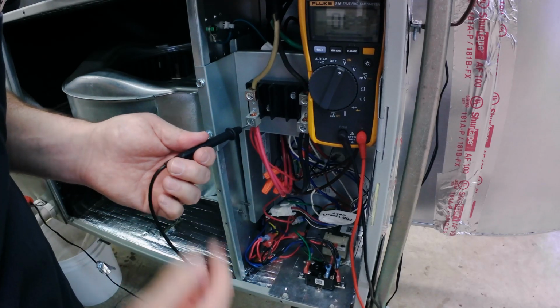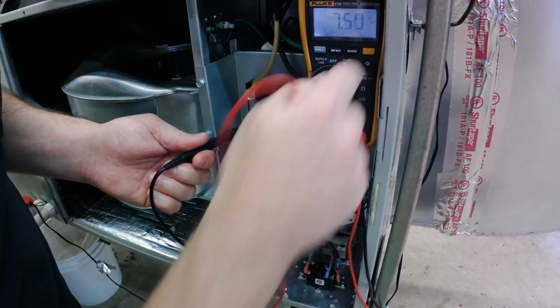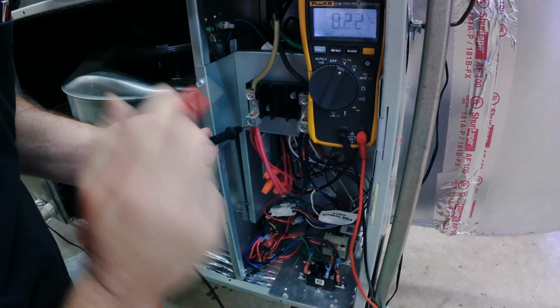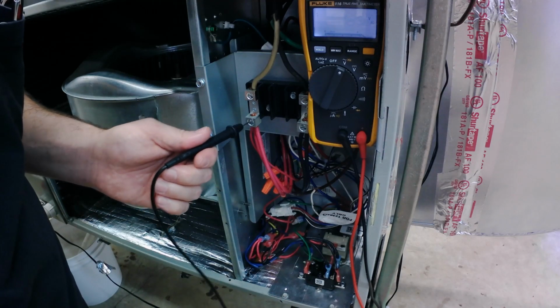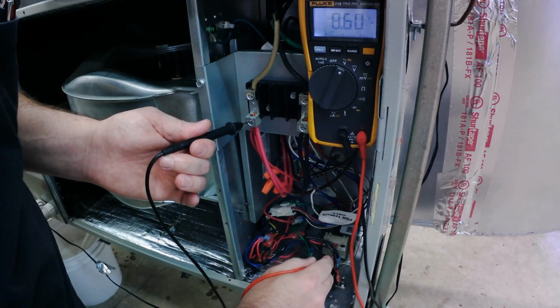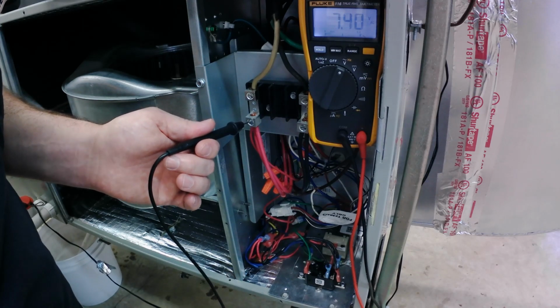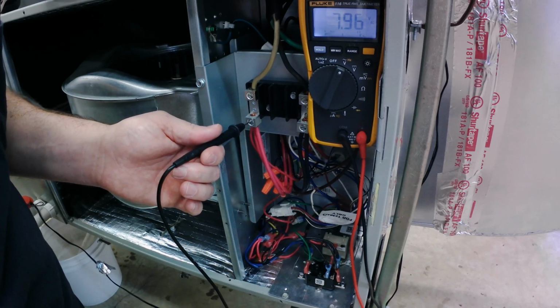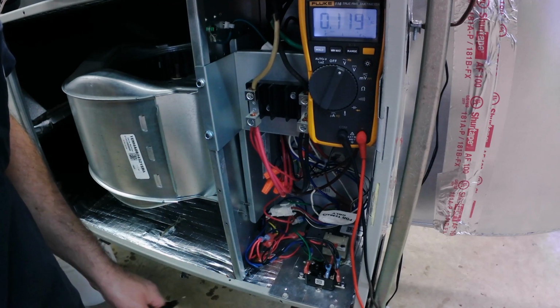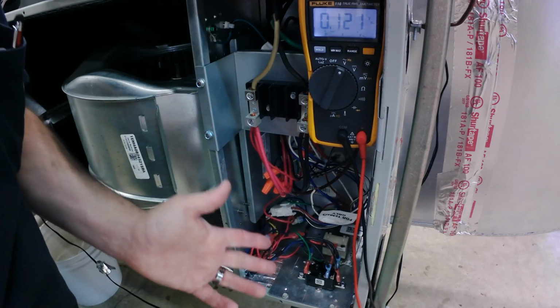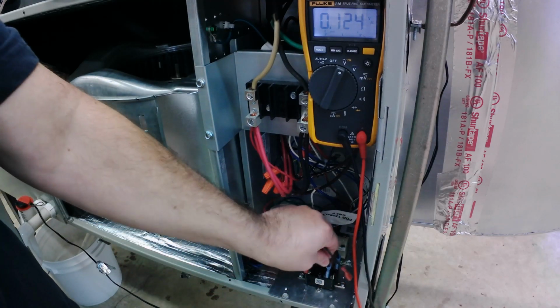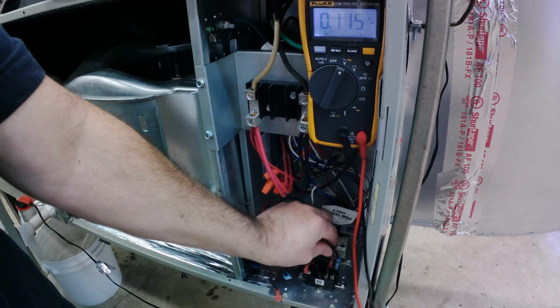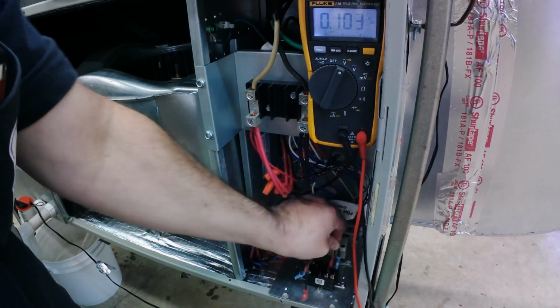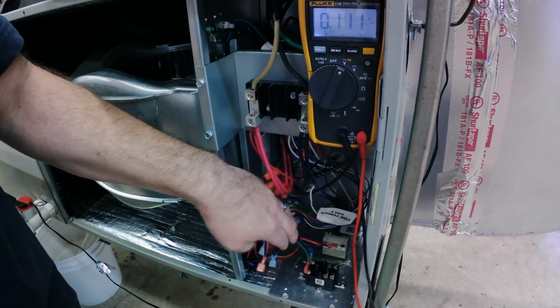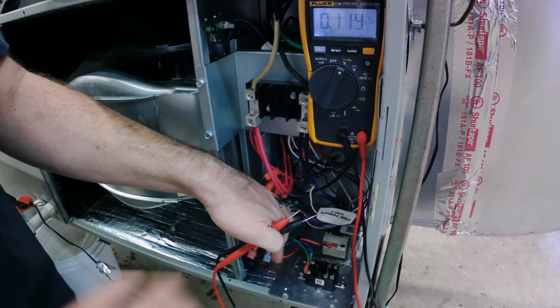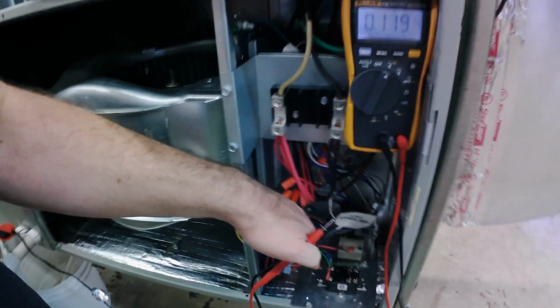So I don't know how it is in your particular setup, but if you will reference the terminal block and find out L1 and L2, you can leave one lead there and follow power in and out of those switches. And when it goes in and doesn't come out, that might be part of your problem. But in this case, I've got the power on. Another way you could do this is if you were to take the wires off, right? A lot of guys are going to get me on this, right? I have disconnected the high voltage completely from this relay, all right? I'm going to move you so you can see it.